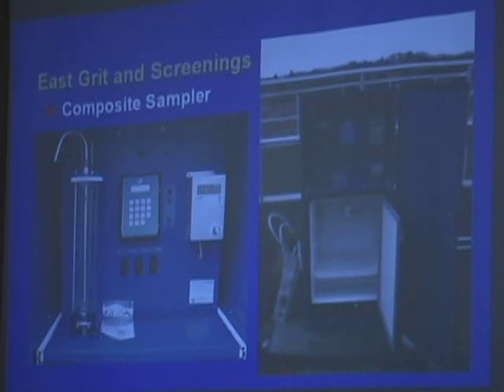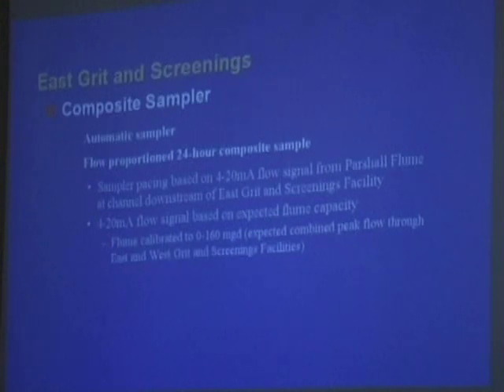There's a control pad. I believe this is identical to the system that we are running right now. The sampling chamber is located on the left-hand side of the control pad here. There's a heater within the unit itself, within the enclosure itself, in order to maintain the electronics in a dry condition and keep the samples from freezing. And below the sampler mechanism itself is the refrigerator for maintaining the sample. Sampler, as I indicated, it's a 4 to 20 milliamp signal coming into it for a flow proportion sample.